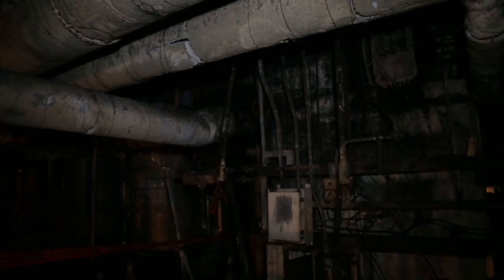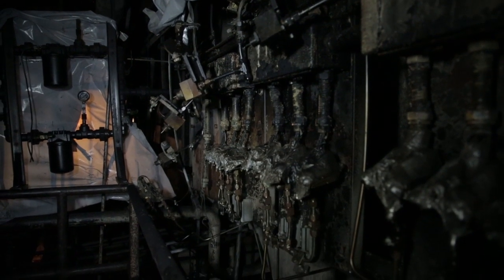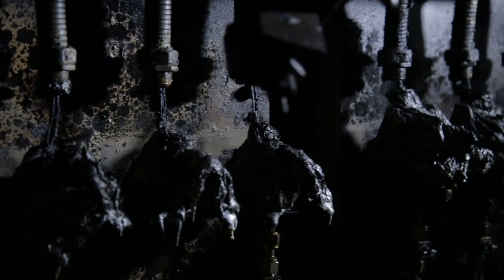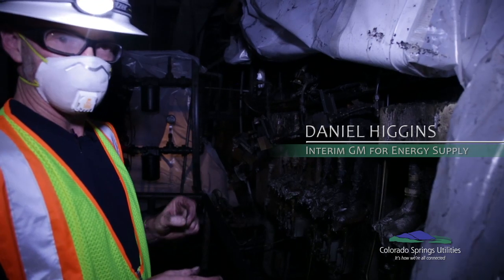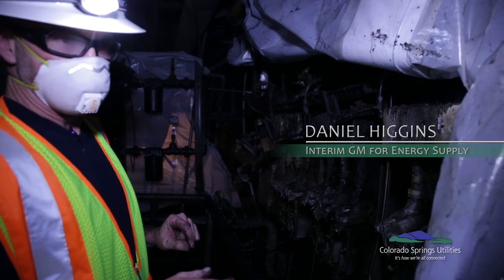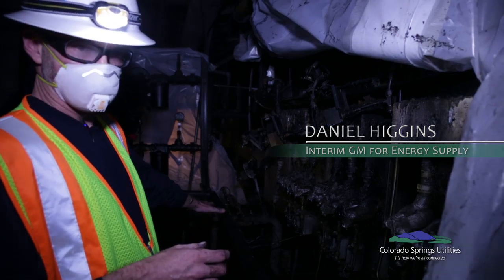So when all three units tripped, we knew immediately. This is believed to be the area where the lubricating oil came out of the system and came into contact with something hot enough to serve as an ignition source. The specific source of the ignition isn't known, but the area of ignition is believed to be down and below me to the left.